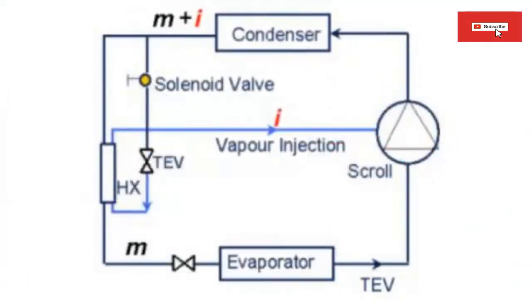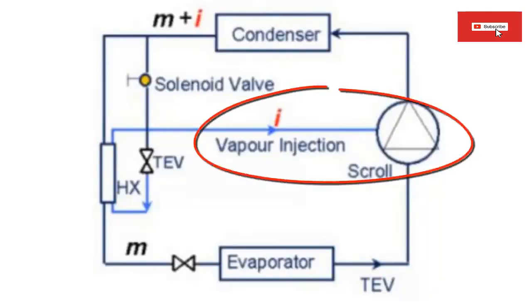1. The vapor injection installation is recommended for all scroll compressors used in low temperature applications. 2. Vapor injected scroll compressors are equipped with a connection for the operation of the economizer system.